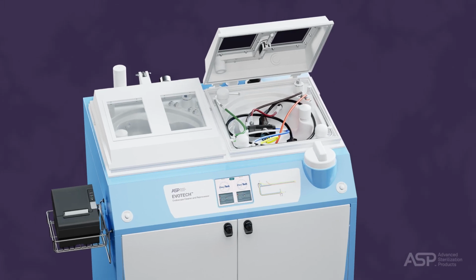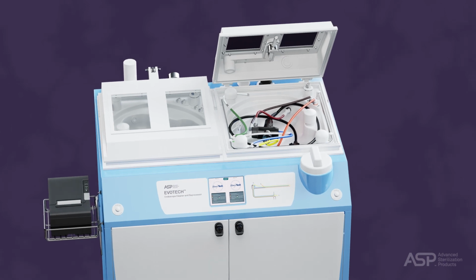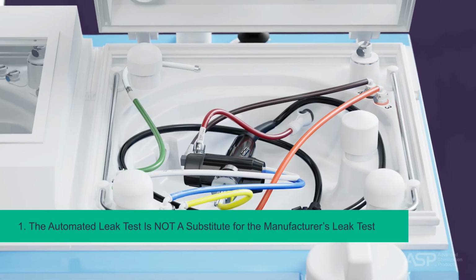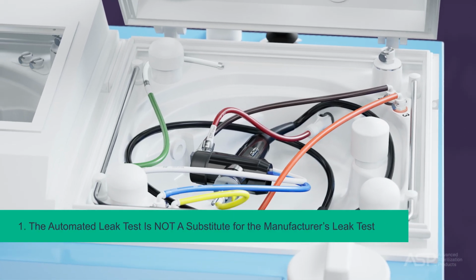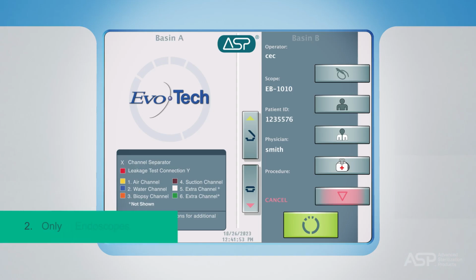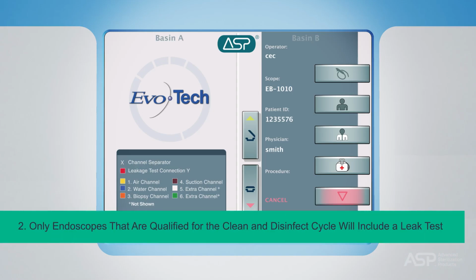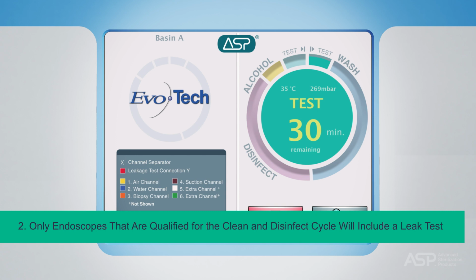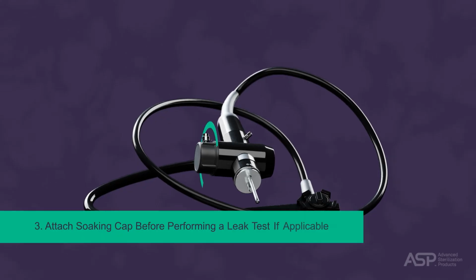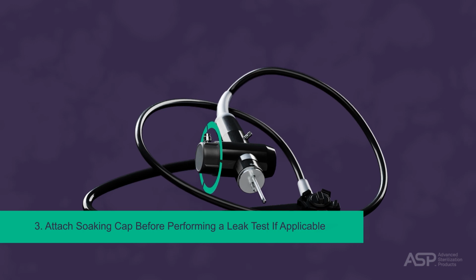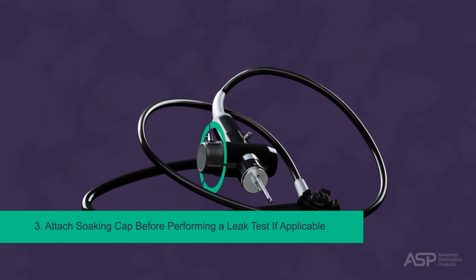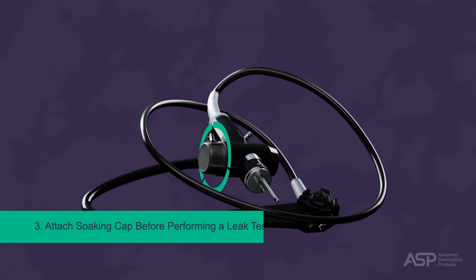Be aware of 3 key points regarding leak testing. First, the automated leak test is not a substitute for the manufacturer's leak test. Second, only endoscopes that are qualified for the clean and disinfect cycle will include a leak test. The connection diagrams and system software will let you know if a leak test is applicable. Third, if you are using an endoscope that requires a soaking cap for reprocessing, attach the cap before performing a leak test.